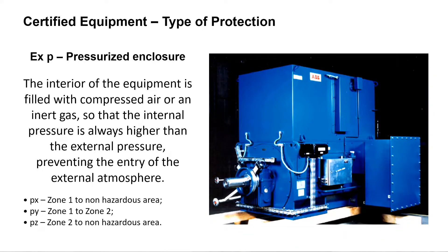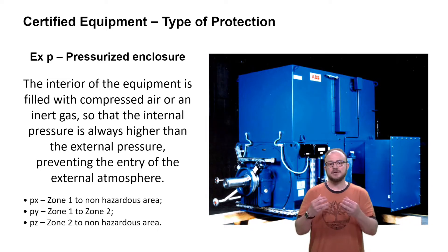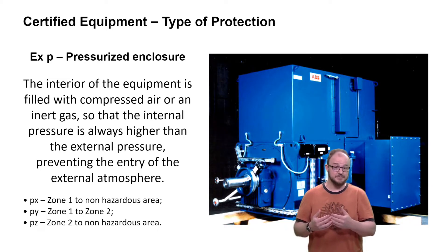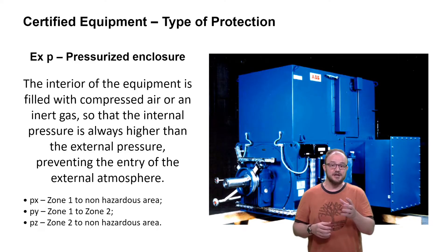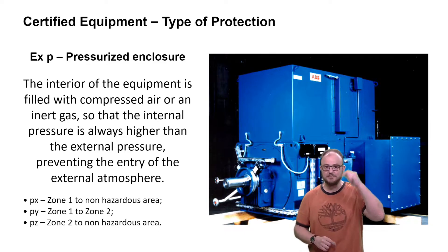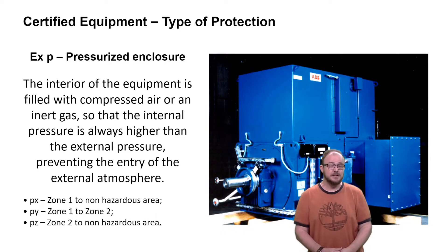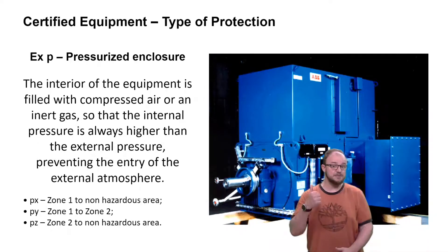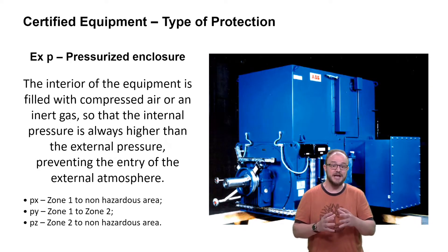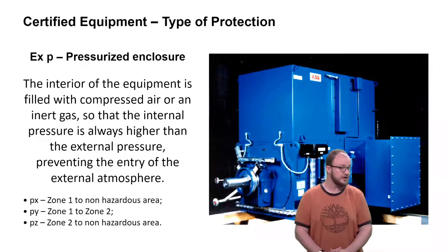We also have the pressurized enclosure. It's very useful when talking about motors because, besides protection against the explosive atmosphere, the compressed air also provides an internal cooling system for that motor. So it's very useful — it keeps the equipment safe and also extends the lifetime of the equipment by cooling it during operation.